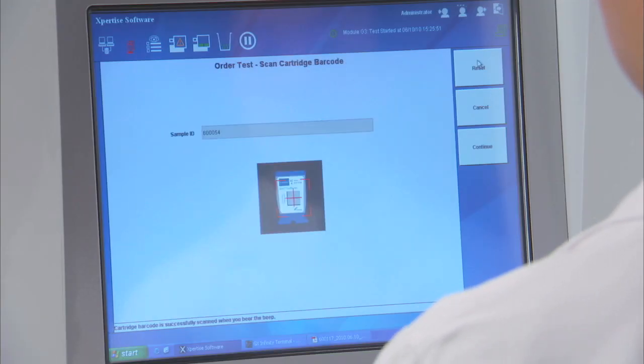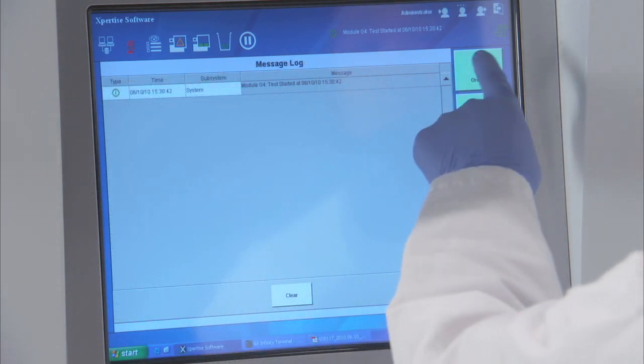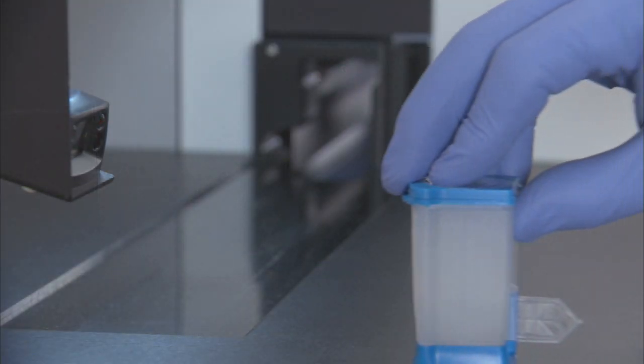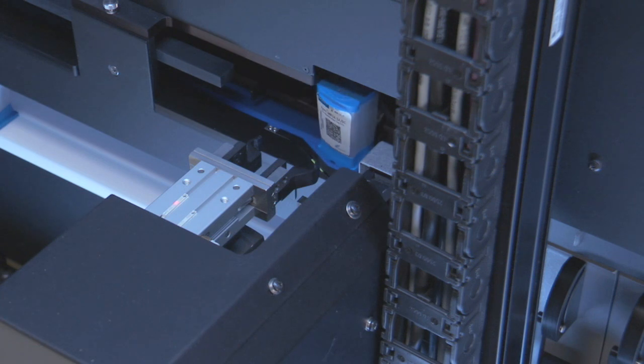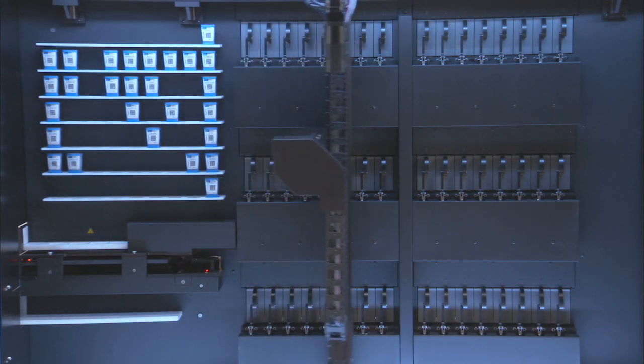Driven by our Xpertise software — the intelligence of the system — offering comprehensive sample management, system operation, and result reporting. This is where the cartridge barcode is first scanned. The bench scanner allows you to rapidly scan patient or sample ID and each unique cartridge. A second scanner located on the gantry will later scan, confirm identity, and log the sample into the system prior to placing the cartridge into a module.